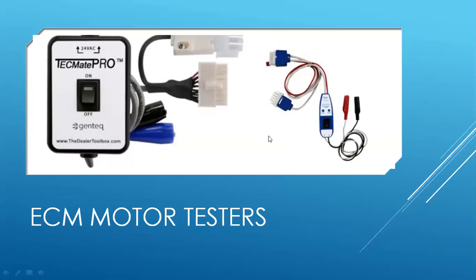So what I like about an ECM motor tester is if I have that with me and I question whether it's the motor or the module, instead of having to really dig into it, I can unplug the 16-pin or 4-pin connection, plug this in, hook up 24 volts, and I know really quickly whether it's the motor or it's the board. So for $50, I can save myself a ton of aggravation and get right to the root of the problem within seconds, or a trip to the van and back. I always carried mine with me, but the days of struggling to figure out whether it's the motor or the module disappear with one of these two testers here.